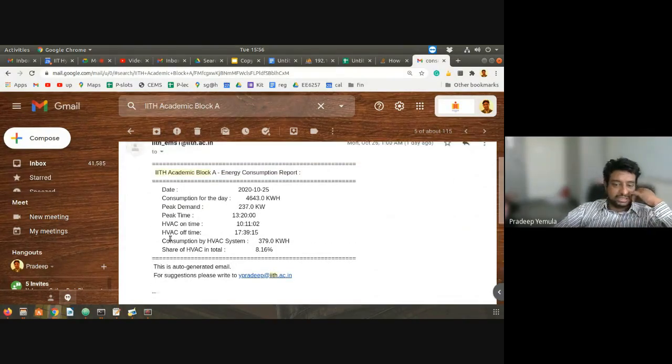So here what it's saying: date, consumption for the day 4643, peak demand is 237 kilowatt, what is the peak time, HVAC on time, HVAC off time, total consumption of HVAC system 379 kilowatt hour. See, sometime back what we calculated, 399 we calculated, right? So this is 379 for 25th October.